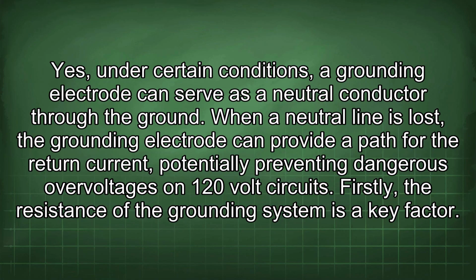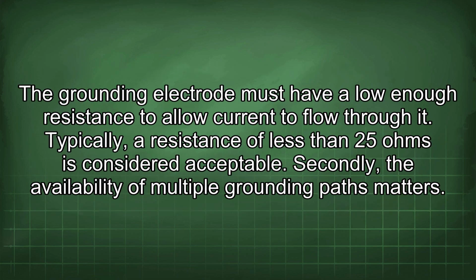Yes, under certain conditions, a grounding electrode can serve as a neutral conductor through the ground. When a neutral line is lost, the grounding electrode can provide a path for the return current, potentially preventing dangerous overvoltages on 120-volt circuits. Firstly, the resistance of the grounding system is a key factor. The grounding electrode must have a low enough resistance to allow current to flow through it. Typically, a resistance of less than 25 ohms is considered acceptable.